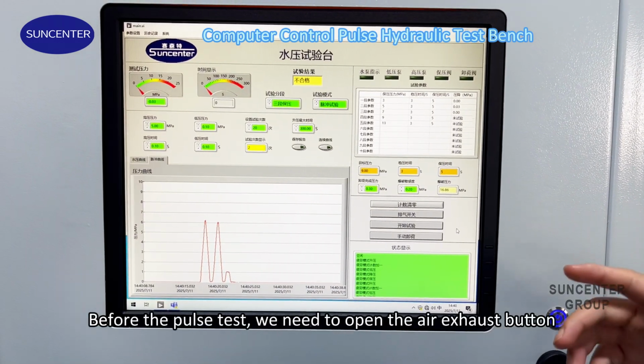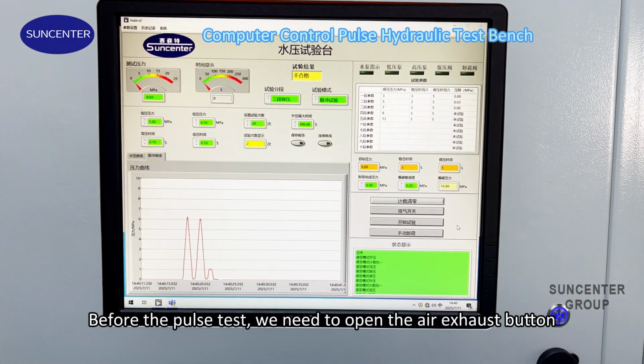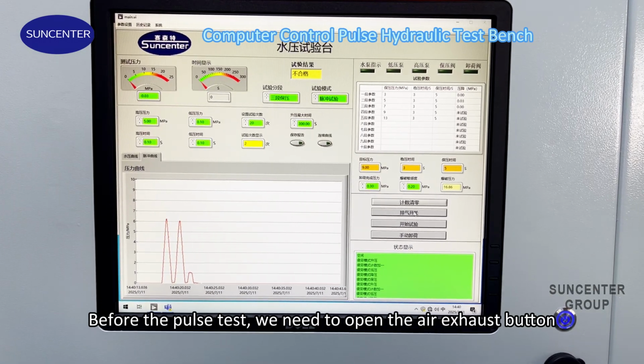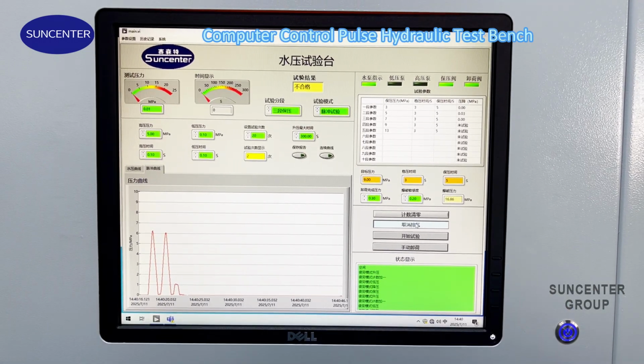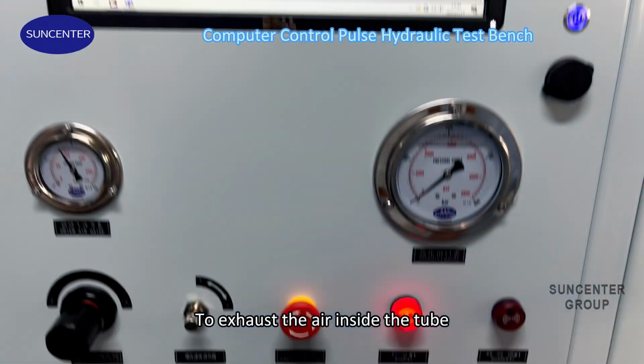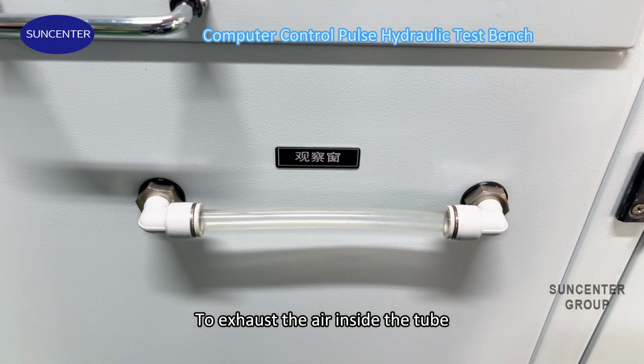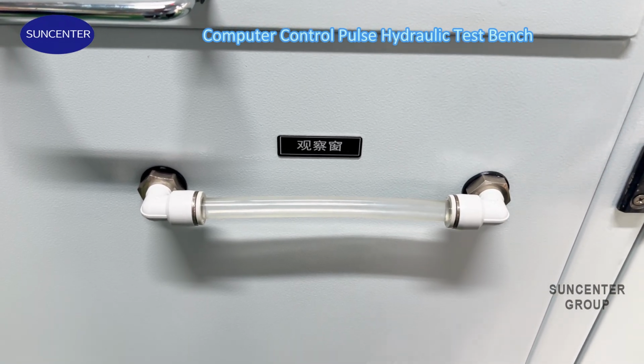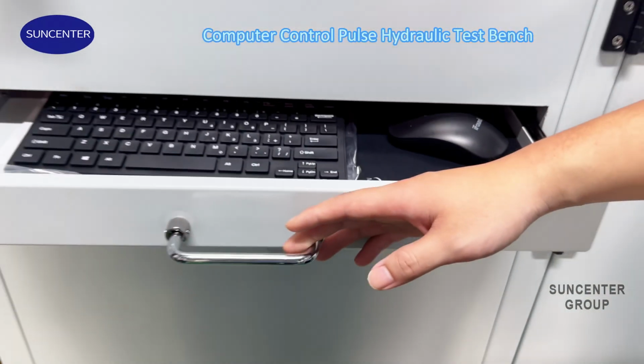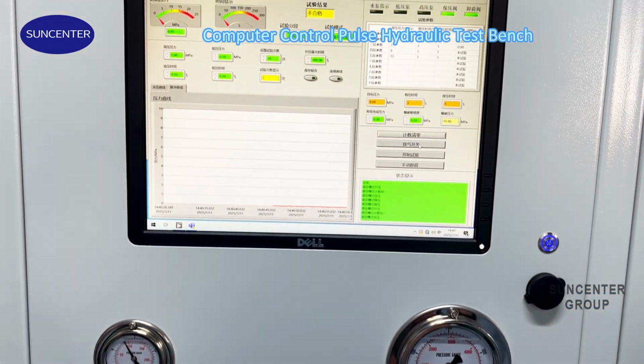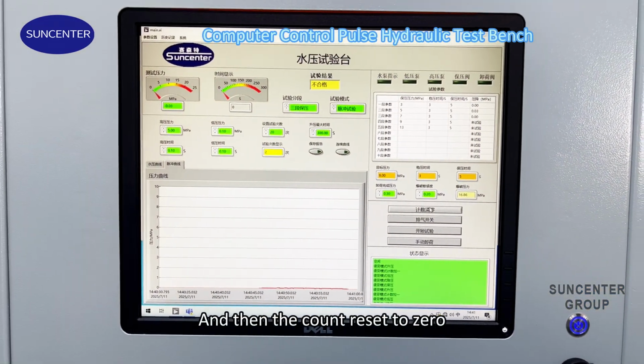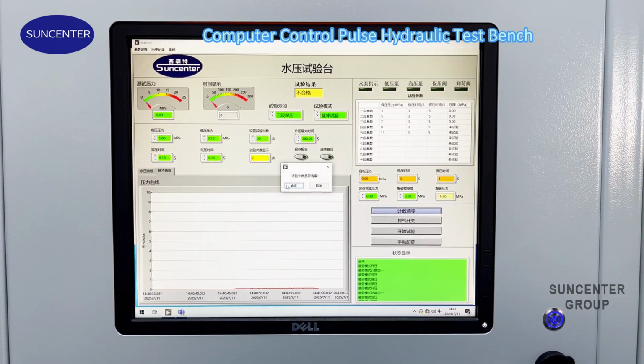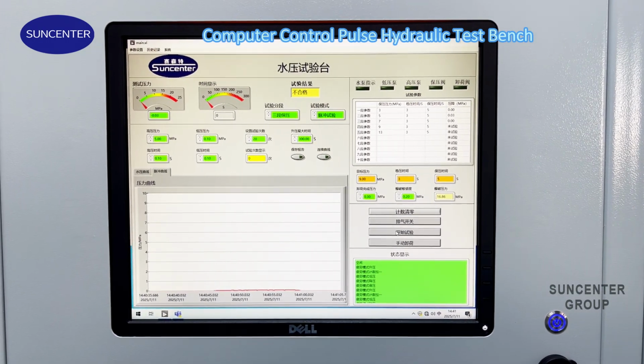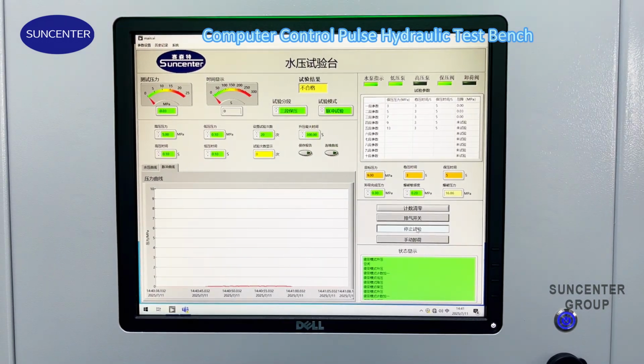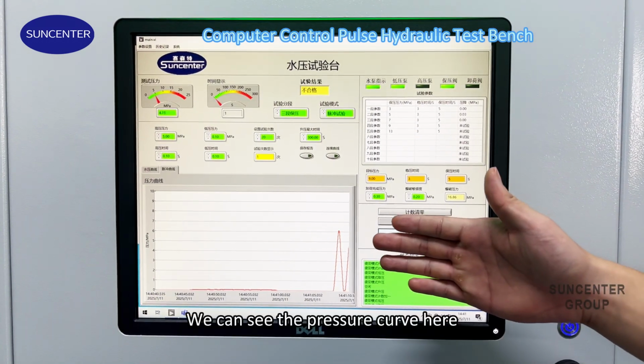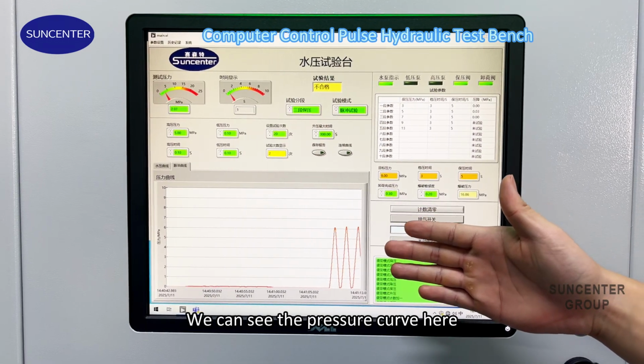Okay, before the pulse test, we need to open the air exhaust button to exhaust the air inside the tube. And then count reset to 0. Then we can open the pulse test. You can see the pressure curve here.